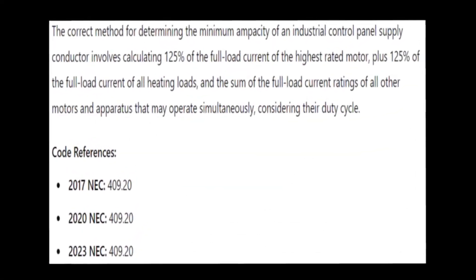The correct method for determining the minimum ampacity of an industrial control panel supply conductor involves calculating 125% of the full load current of the highest rated motor, plus 125% of the full load current of all heating loads, plus the sum of all full load current ratings of all other motors and apparatuses that may operate simultaneously. You can also consider duty cycle.